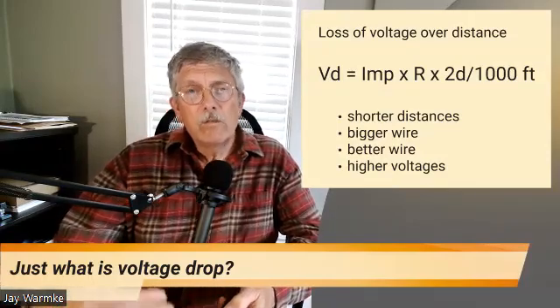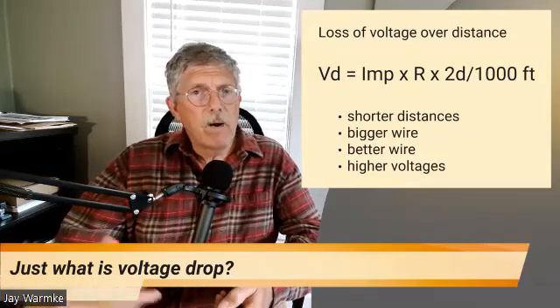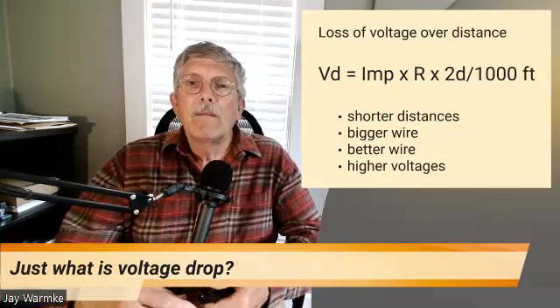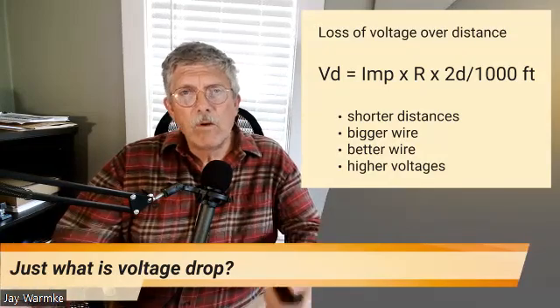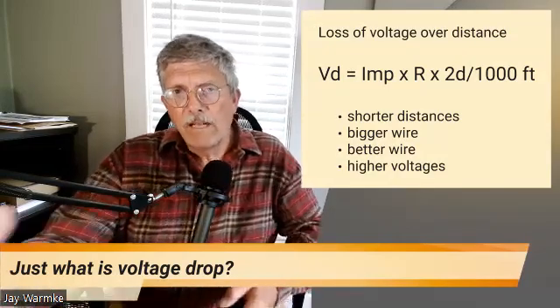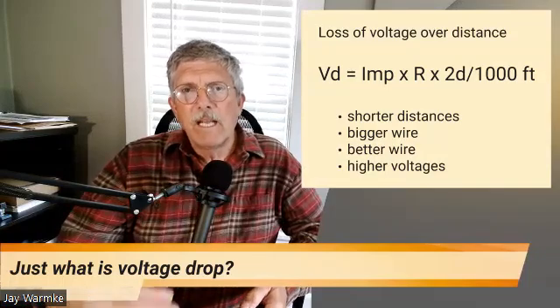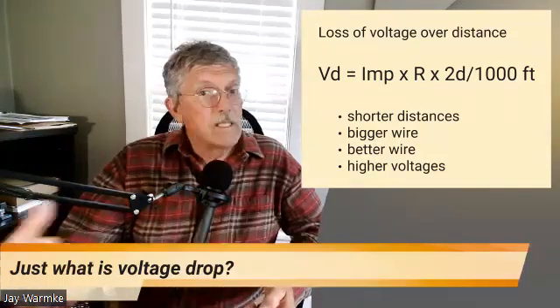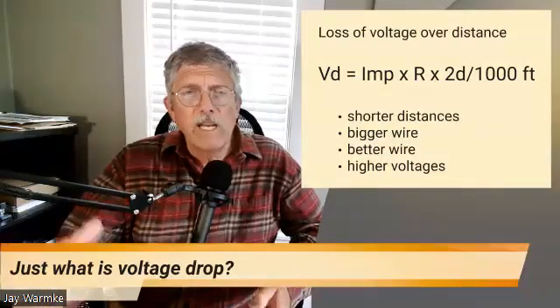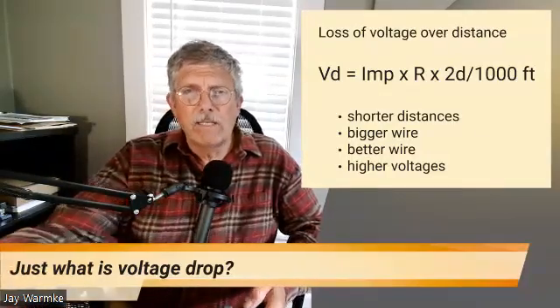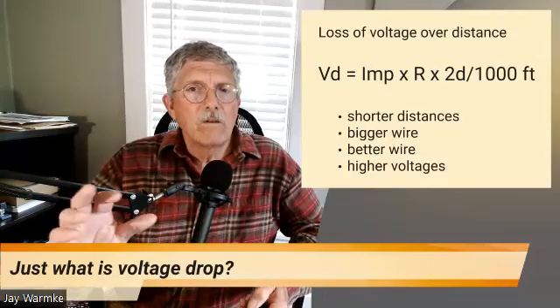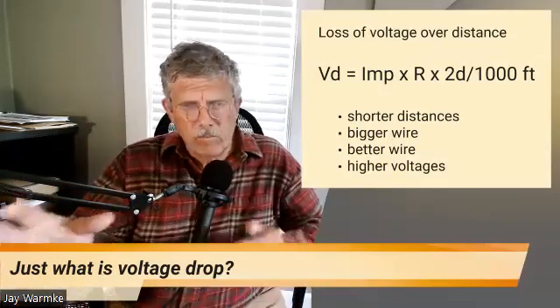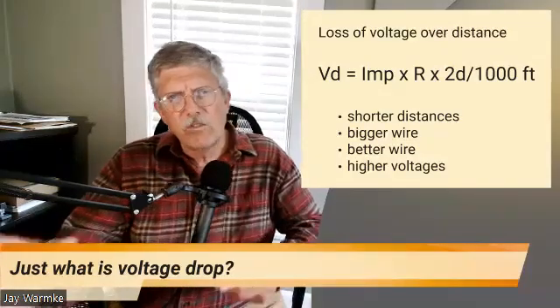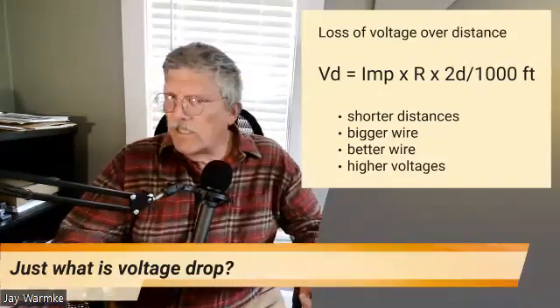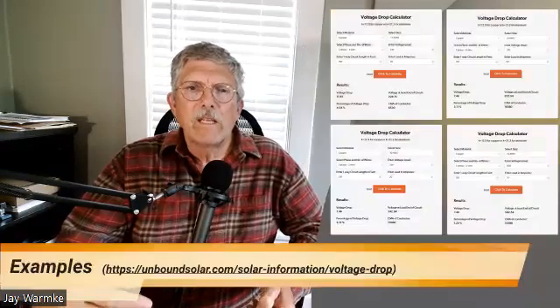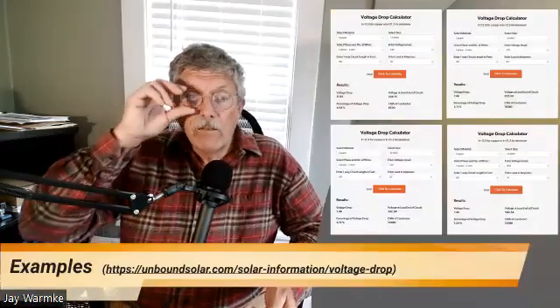Better wire, using copper versus aluminum, is primarily your choice. And higher voltages: the higher the system voltage, the less impact voltage drop has on the system as a percentage of loss. It doesn't change the amount of voltage drop, but it does change the percentage of power that's lost due to voltage drop. The purpose of this wasn't really to get into how to calculate voltage drop or how to mitigate it, other than that you just throw in bigger wire. That's usually the thing.